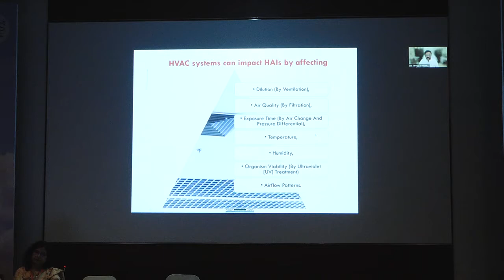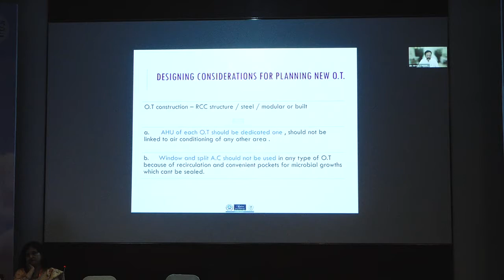Ideally, the operation theatre should be RCC construction, steel, or modular build, and the AHU has to be dedicated, not linked to the air conditioning of other areas. Generally, window and split AC should not be used in any type of OT because they are only recirculation units, and there can be convenient pockets for microbial growth which cannot be sealed.